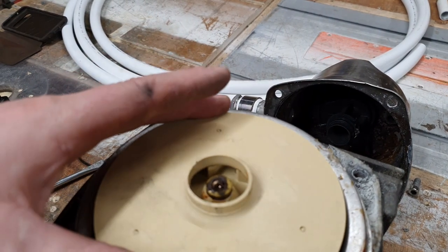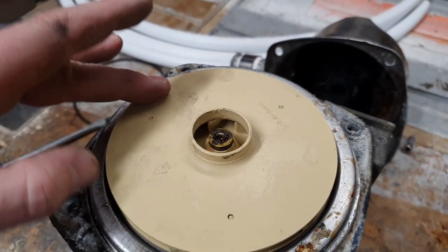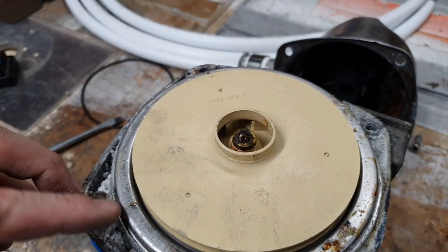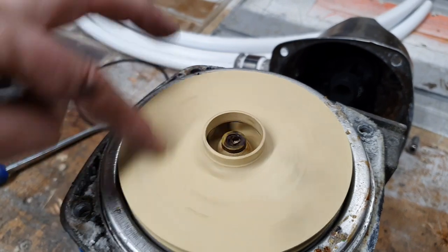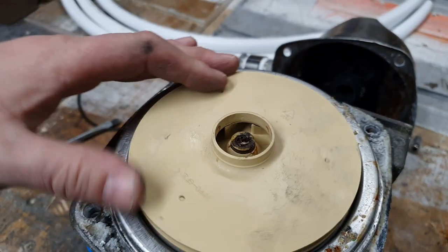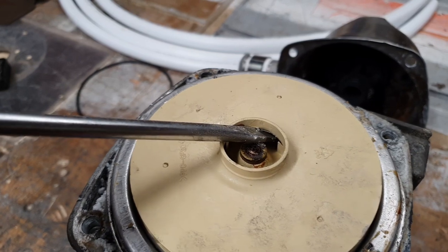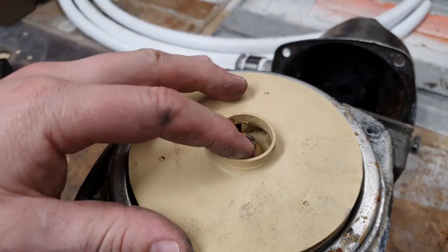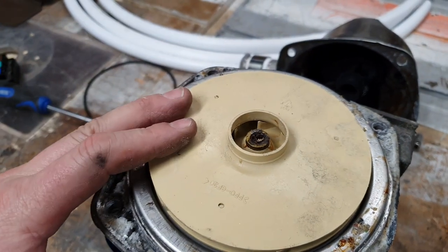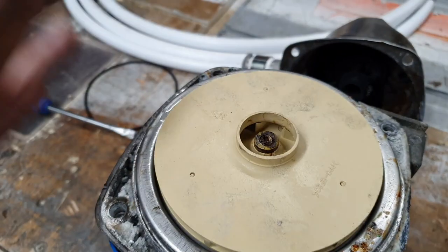Normally what happens on these pumps if you're using them in an acid environment - which we have been doing - there's one pump for caustic and one for acid. The acid tends to eat away at this little brass bushing, and that wears away completely. The drive shaft that runs through the bell housing into the pump motor is stainless steel so that's fine. There's some cracking happening there as well. You can order these brass bushings as spares from Clark for about 10 to 15 quid each - saves you buying a new pump.